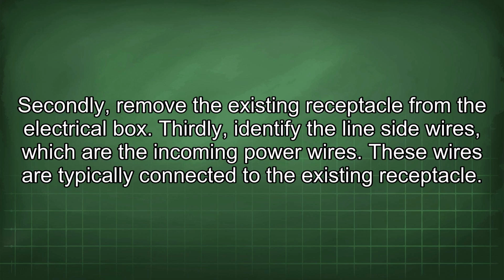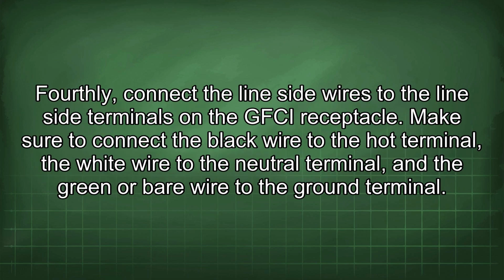Thirdly, identify the line side wires, which are the incoming power wires. These wires are typically connected to the existing receptacle. Fourthly, connect the line side wires to the line side terminals on the GFCI receptacle. Make sure to connect the black wire to the hot terminal, the white wire to the neutral terminal, and the green or bare wire to the ground terminal.